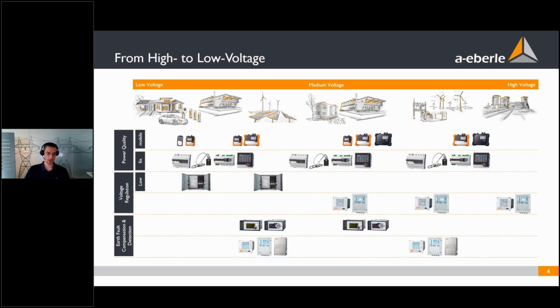Then in the middle row, there's voltage regulation. As you see, two different product groups as well. One for the low voltage regulation that is quite new. This product group is one of the younger ones. And the other voltage regulation product group for medium and high voltage regulation has the REG-D, which is the product that Eberle first developed. And lastly, in the bottom rows, there is earth fault compensation and detection, which is done by our product group, EOR-Sys.